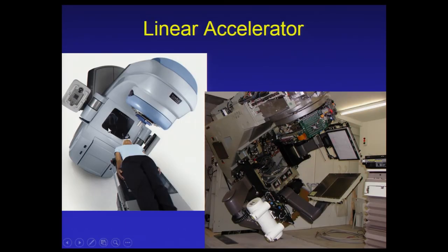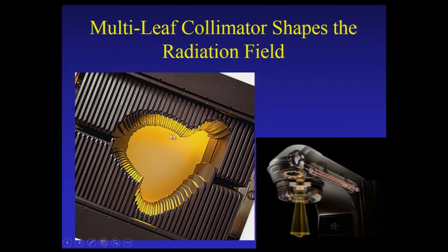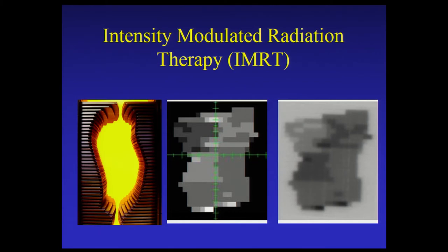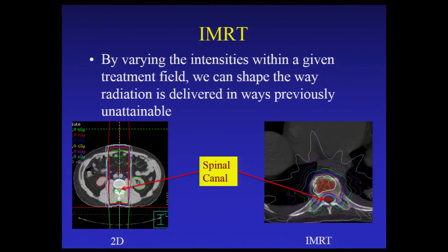The tool used to deliver radiation to the spine is called a linear accelerator. The radiation is produced and exits the treatment head, targeted to the patient. As it exits, the beam is shaped by lead leaves called multi-leaf collimators. An advance from the 1990s involved modulating the intensity of the radiation beam — these lead leaves can move while the beam is on, forming different shapes and changing the beam's intensity as it points to the target in the body. This allows us to shape the radiation in ways that hadn't been done before.